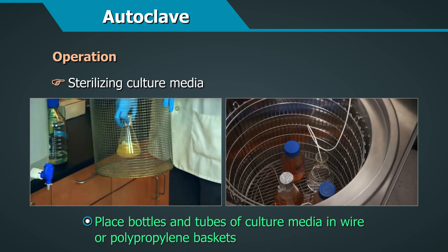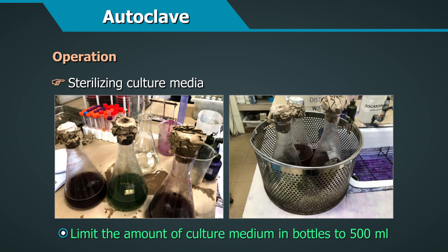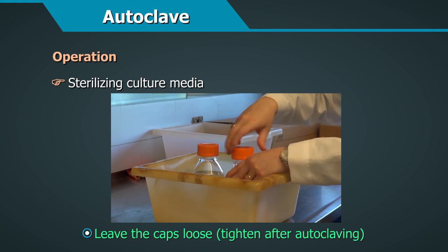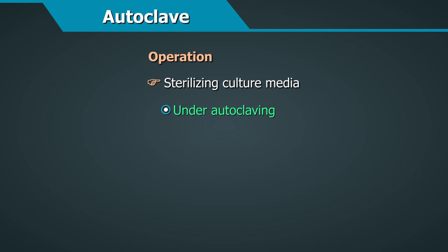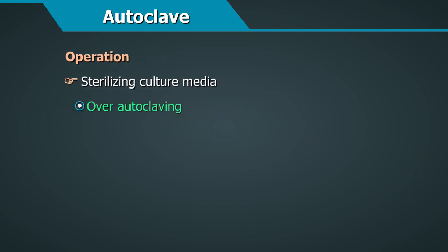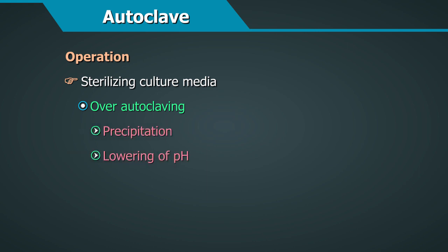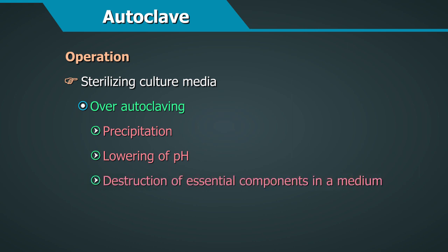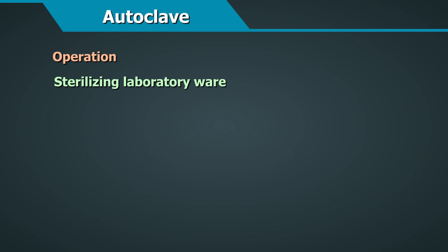When sterilizing culture media, place bottles and tubes in wire or polypropylene baskets. Limit the amount of culture medium in bottles to 500 ml and leave the caps loose, tightening them after autoclaving. Always sterilize the media at the correct temperature and for the correct length of time as instructed. Under-autoclaving can result in an unsterile medium, whereas over-autoclaving can cause precipitation, lowering of pH, or destruction of essential components.